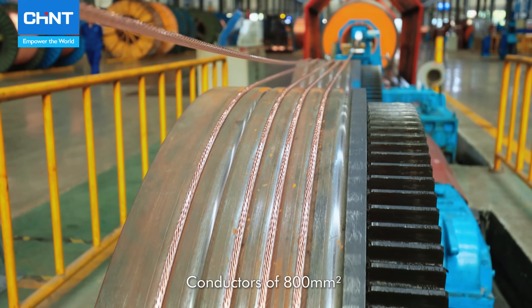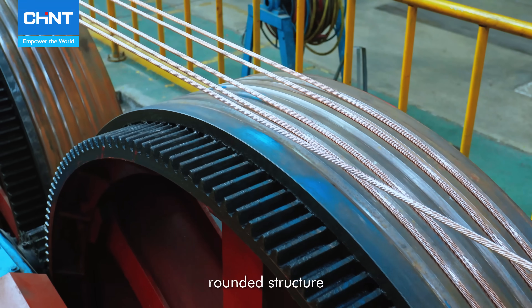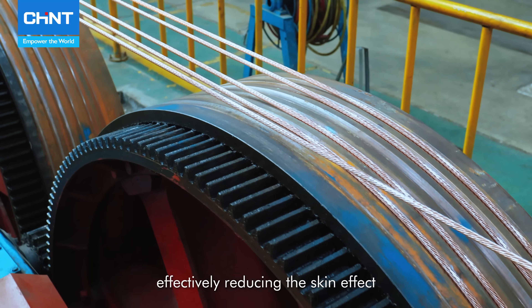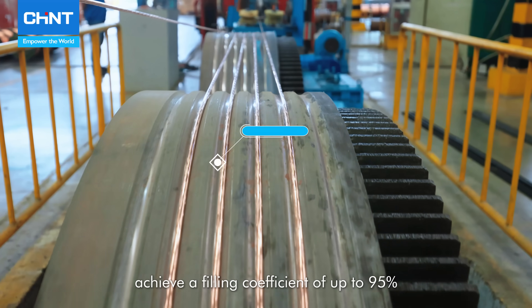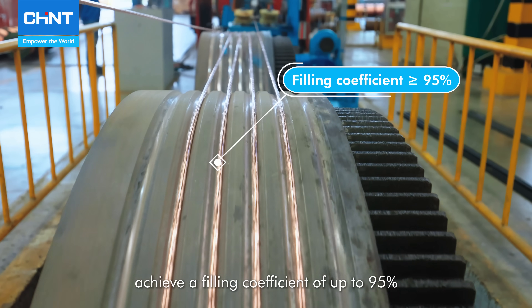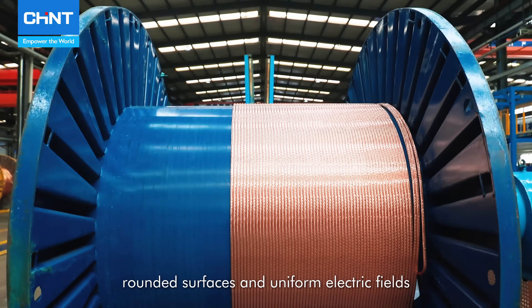Conductors of 800 mm² and above use Milliken conductors for a stable, rounded structure, effectively reducing the skin effect. Shaped wire processes achieve a filling coefficient of up to 95%, with smooth, rounded surfaces and uniform electric fields.